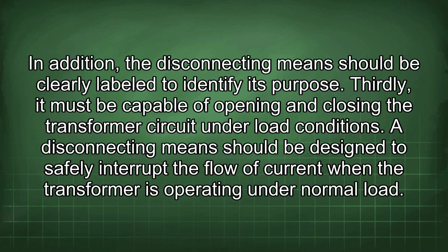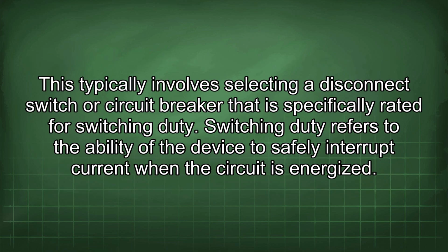Thirdly, it must be capable of opening and closing the transformer circuit under load conditions. A disconnecting means should be designed to safely interrupt the flow of current when the transformer is operating under normal load. This typically involves selecting a disconnect switch or circuit breaker that is specifically rated for switching duty. Switching duty refers to the ability of the device to safely interrupt current when the circuit is energized.